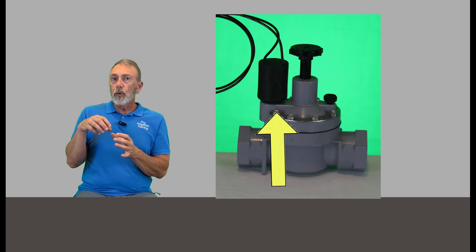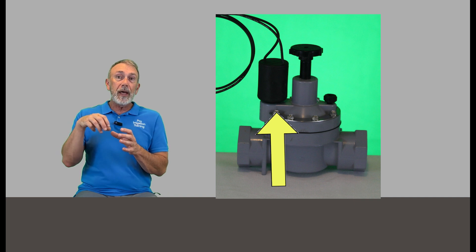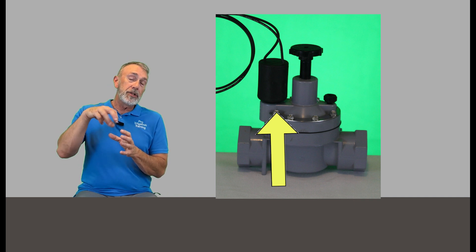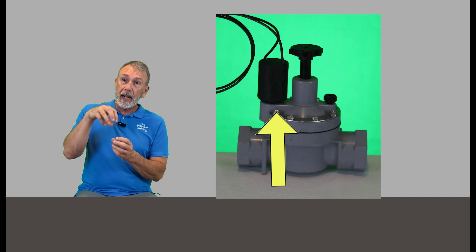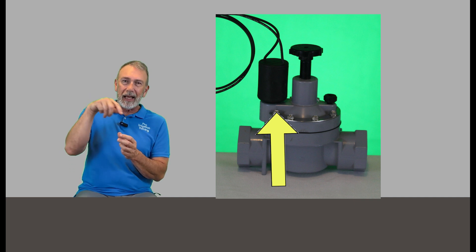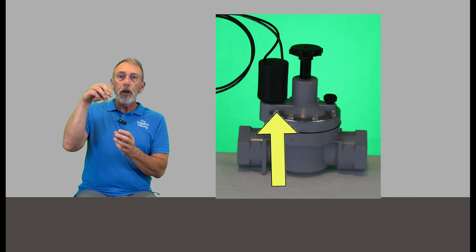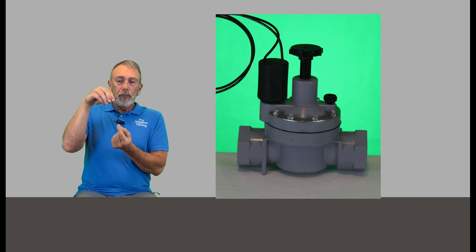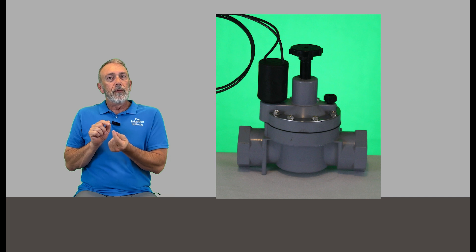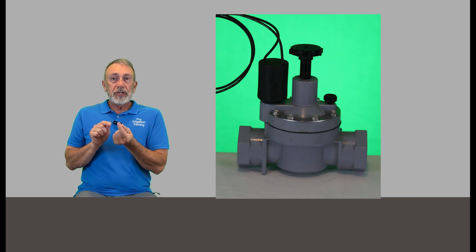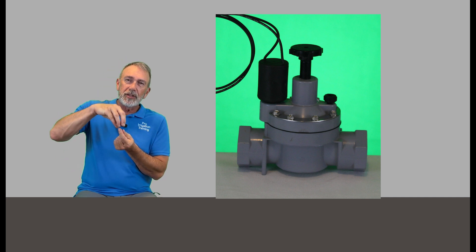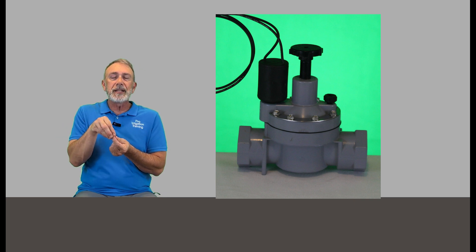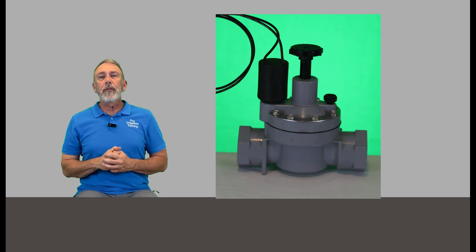You can manually actuate a valve, a solenoid valve by unscrewing your solenoid. Don't take it all the way off and be careful, be slow about it because it's only got like three loops of the threads there. And if you take it all the way off, sometimes there's a little tiny hole inside of there that if the pressure's on, it could push enough water through it to where you can't get that solenoid to seat back down and you can cross thread those plastic threads.